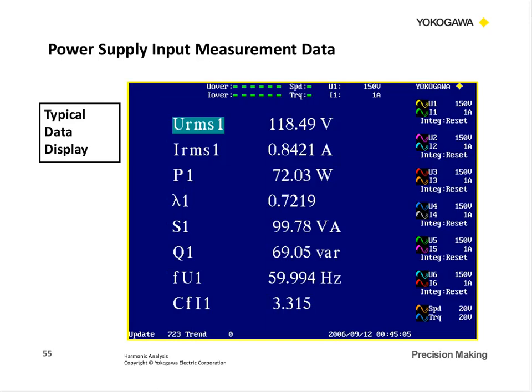So we look at typical data, which might be the RMS value of voltage and current. We've got the true power measurement. We've got the power factor. Remember how power factor was calculated? Watts divided by VA. So here's your watts divided by the VA. If you've got a calculator, you can check that real quick, but that looks about right, doesn't it? This is the VAR, our frequency. And this was a crest factor.